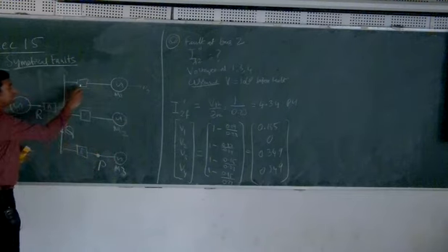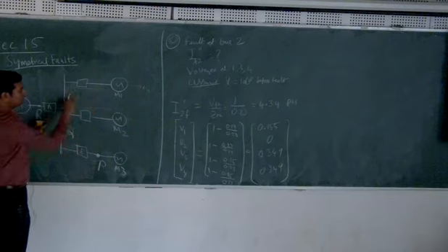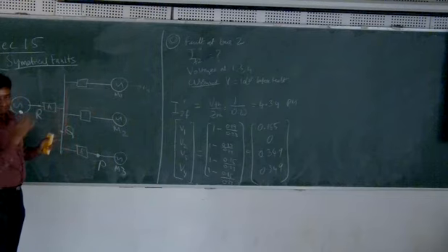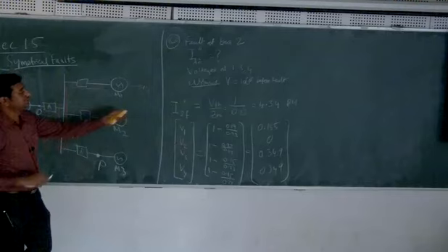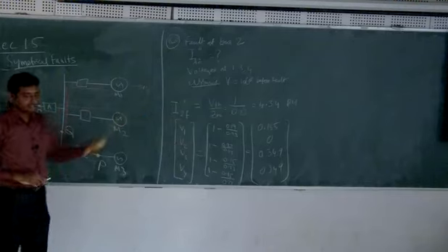So even if I don't open this, initially there is a fault current, but after that initial short period, further current will not come because this other side is here. So more importantly, A should operate first, and the other things, even if they see fault current for some time, they will not. So this kind of thing. And what if there is a fault in R? If there is a fault in R, same thing. A should operate first.